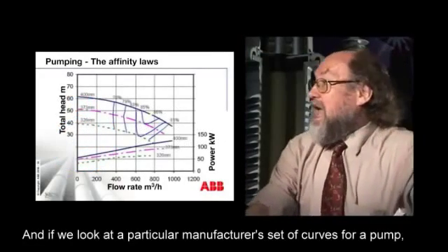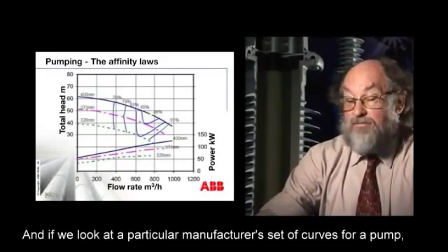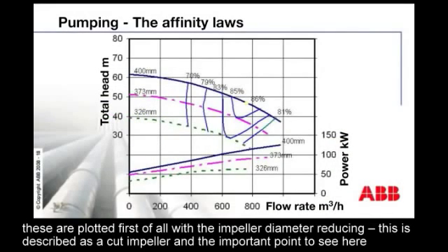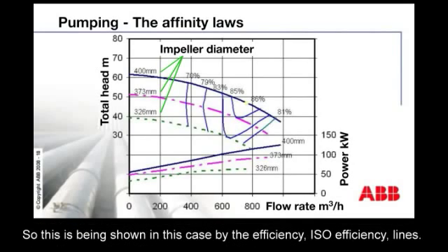If we look at a particular manufacturer's set of curves for a pump, these are plotted with the impeller diameter reducing — described as a cut impeller. The important point to see here is that the flow-head-volume curves all decline, but the efficiency curves actually tend to reduce as the impeller cut increases. This is shown by the isoefficiency lines.